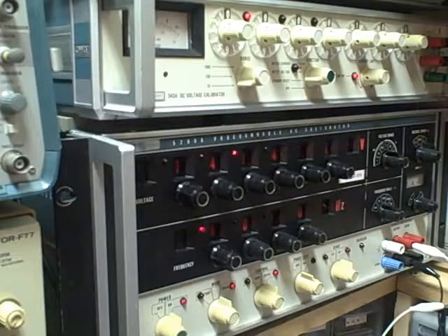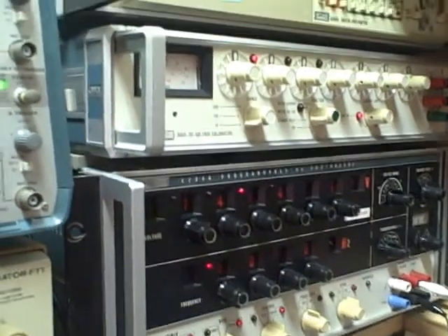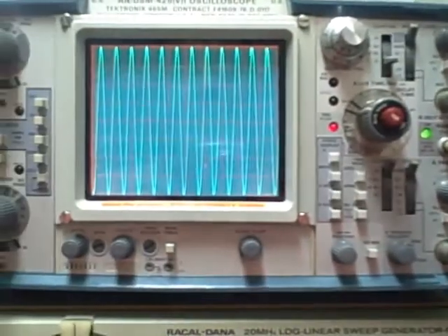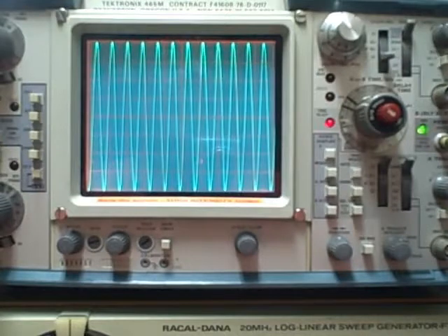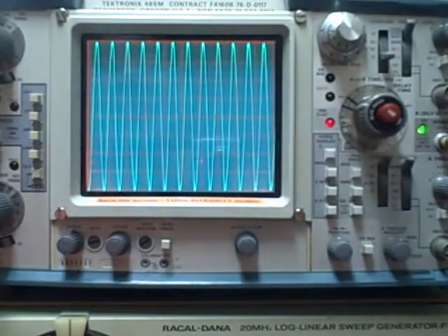capable of producing voltages from a millivolt up to, well, with an external unit I could go up to 1000 volts. This particular unit will go up to 100 AC volts, and we can go from 100 hertz up to a megahertz. Right now we are feeding in a 600 hertz signal, and that signal on the 5 millivolt per division scale, we're up 4 divisions, so that's 20 millivolts peak AC.